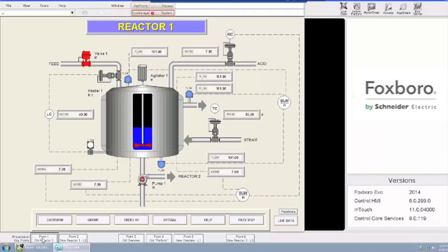The first problem we notice, the very same metric, in this case the color red, is used to indicate that a valve is closed, a pump is stopped, a heat exchanger is on, the agitator is off, and, oh, by the way, this very high priority alarm on a temperature indication requires the operator's immediate attention. When you use the same metric to mean many things, it loses its meaning. Alarm colors should be reserved exclusively for alarm states, never for normal operational states.